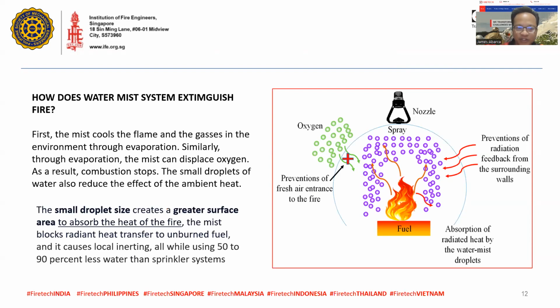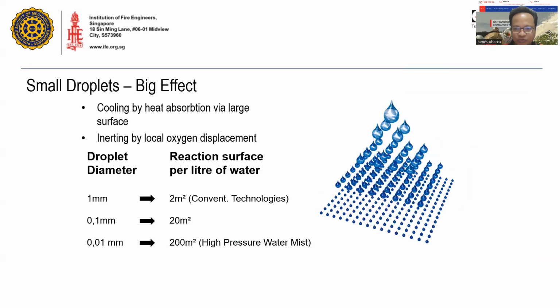Okay, so the small drop size creates a greater surface area to absorb the heat of the fire. The mist blocks radiant heat transfer to unburned fuel and causes local inerting, while using 50 to 90% less water than a sprinkler system.